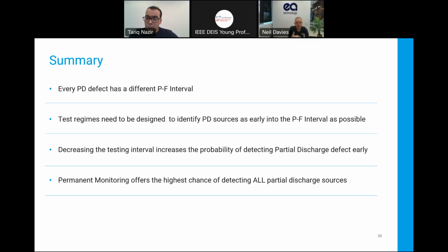So what you then do is you change things and you start looking at what is the risk on the network and what is the criticality of the assets I'm dealing with. So therefore, we're going to reduce our probability of failure on the critical assets by doing more frequent testing or putting a permanent monitor on in that. But on some less critical assets, we will accept that there will be certain instances where we will miss things.